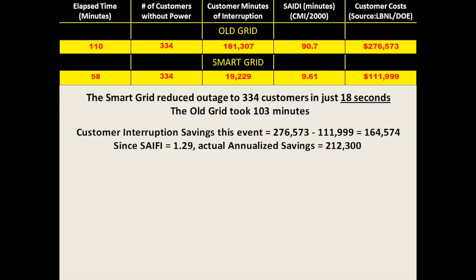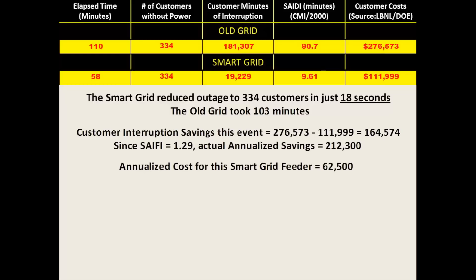This automation isn't free. Five smart devices were added to the feeder, and four were added as ties to other feeders. Using a 30-year life, an 11% cost of capital, and an operations and maintenance charge of 3%, those devices have an annualized cost for this smart grid feeder of about $62,500. That's a pretty good return on investment — spending $62,500 per year to get over $210,000 in savings for customers on the feeder.